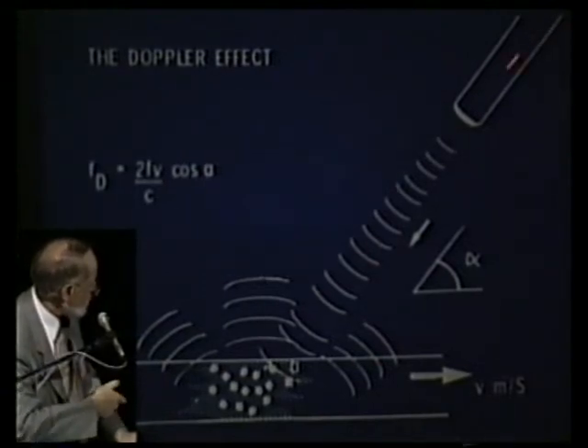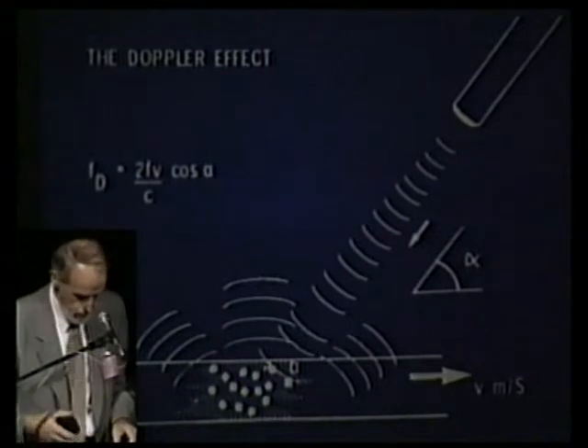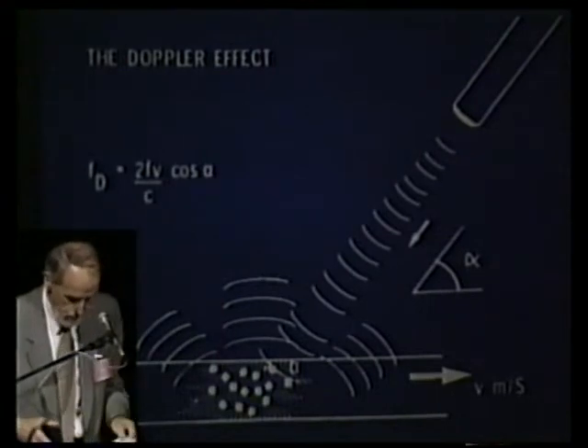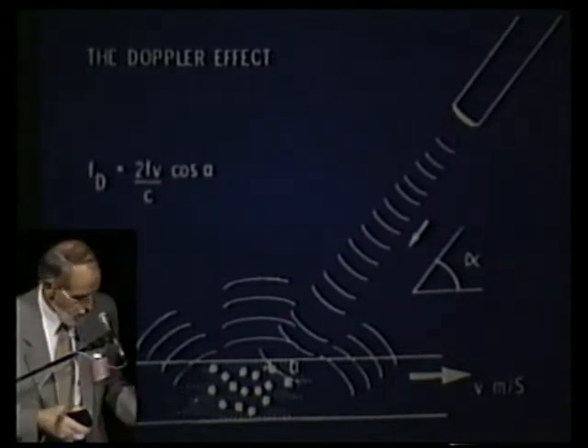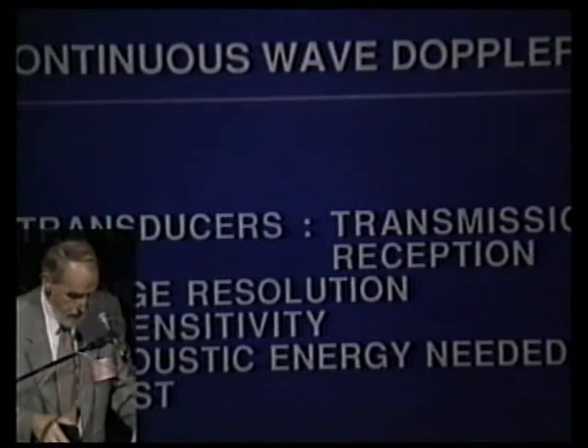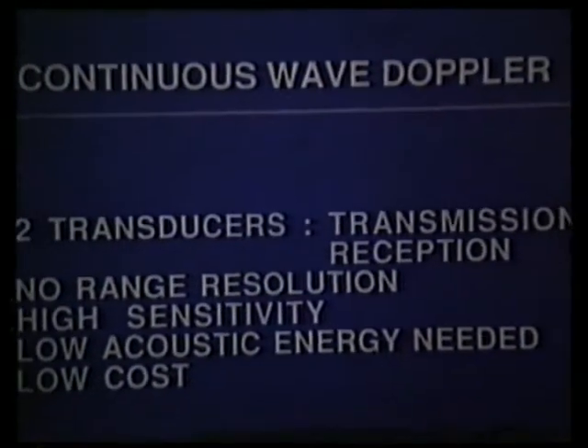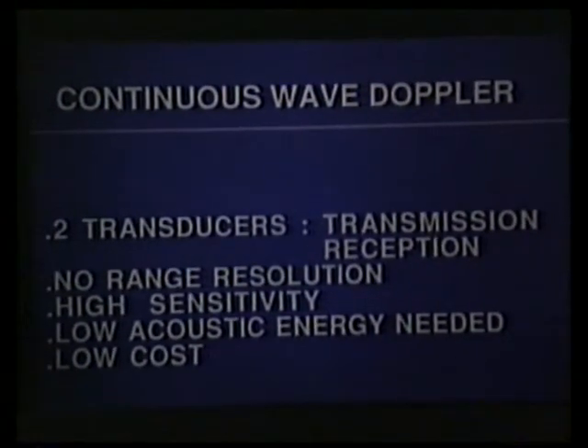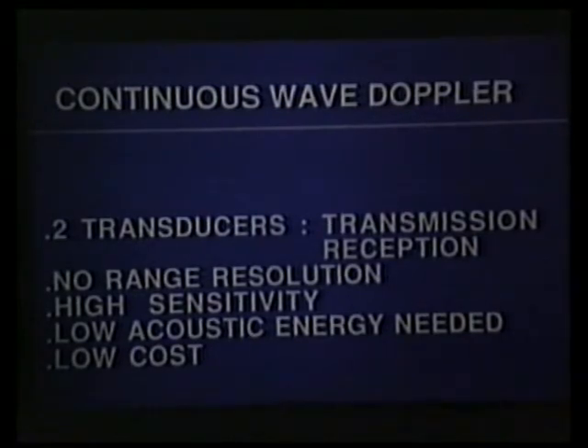Doppler instruments are of two types: the continuous wave instrument, which uses two separate transducers, and the pulsed wave instrument, which uses only one transducer for both transmission and reception.